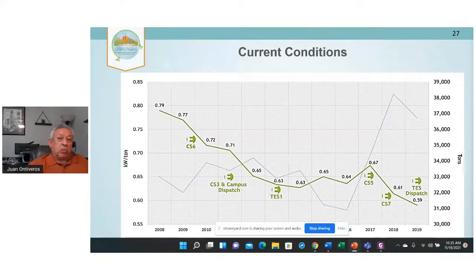This chart shows you a more extensive look at how we've done our performance. In 2008 is when we put in chilling station 6. It was 0.79 kW a ton. The dotted line you see here is the campus, how many tons of cooling we are putting onto campus. You can see how it grew. This period here where it grew was when the medical school was built. So you can see we've been gradually reducing it through the years. And in 2019, we ended the year at 0.59 kW a ton. That's total, including chillers, towers, pumps, everything, the whole campus.